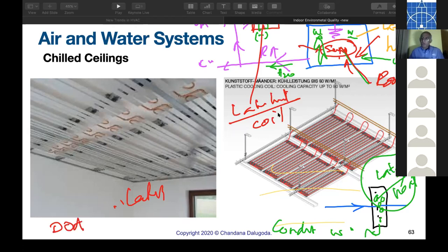DOAS, dedicated outdoor air system, a dedicated outdoor air handling unit must be coupled to this. Now that will send air here with a very low kilogram per kilogram, very low moisture content air, lower than the moisture content in the room, the desired conditions moisture content in the room. So you are sending air whose moisture content is lower than the desired condition air moisture content. So that can absorb water vapor. That's how you remove it.